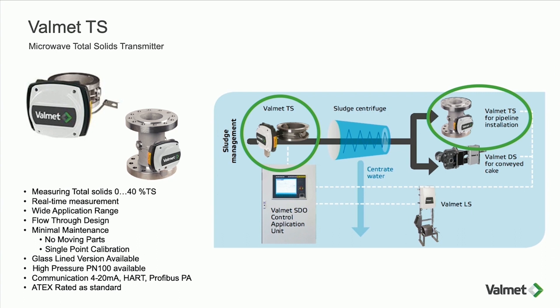It's a very simple device. We use a time-of-flight microwave measurement method — we measure the speed that the microwave passes across a pipe, which has a linear correlation to the amount of solids in the pipe, so we can generally use a single-point calibration. There are no moving parts, so maintenance is very low with no regular maintenance required. In some applications there can be a build-up of fat, so we have a glass-lining version available — that's typically needed at the beginning of the process around primary clarifiers.